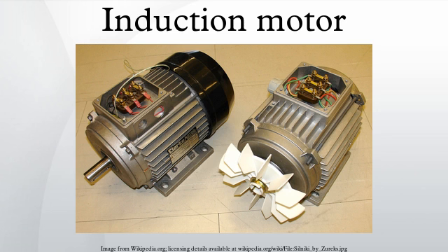Since the short-circuited rotor windings have small resistance, a small slip induces a large current in the rotor and produces large torque. At full rated load, slip varies from more than 5% for small or special-purpose motors to less than 1% for large motors. These speed variations can cause load-sharing problems when differently sized motors are mechanically connected. Various methods are available to reduce slip, VFDs often offering the best solution.